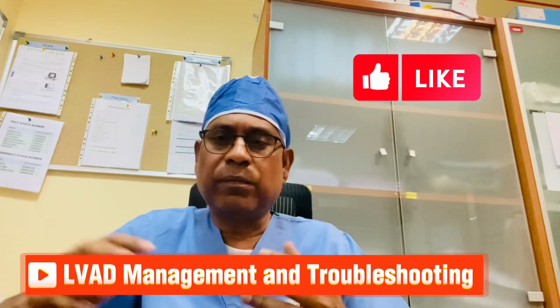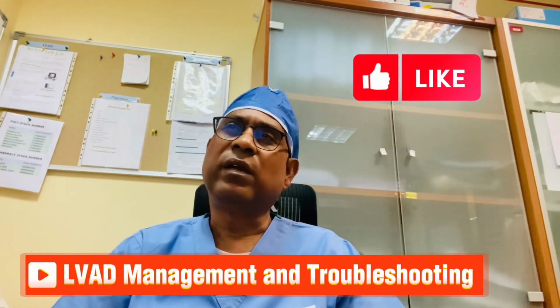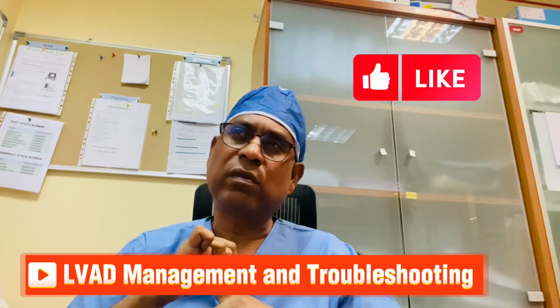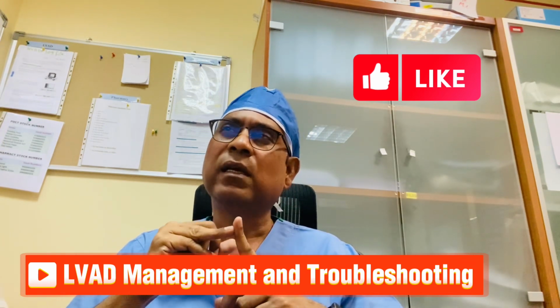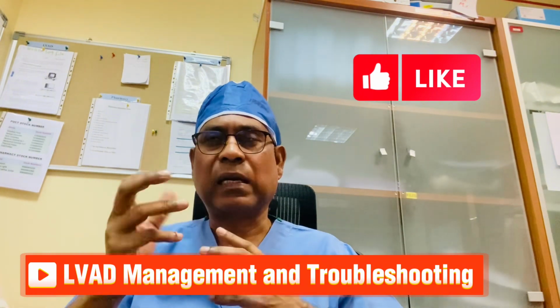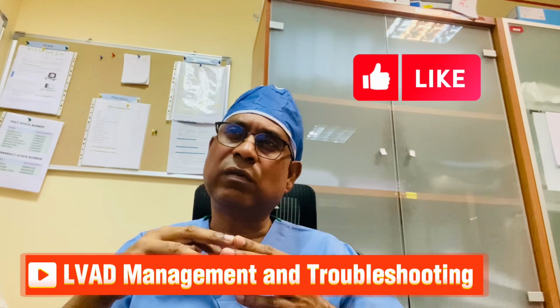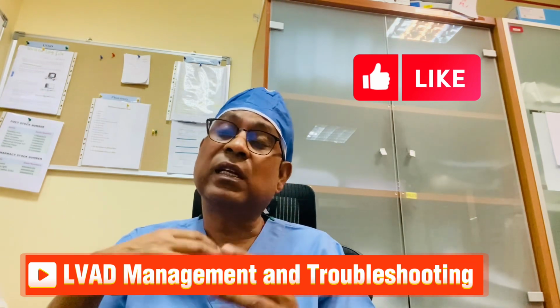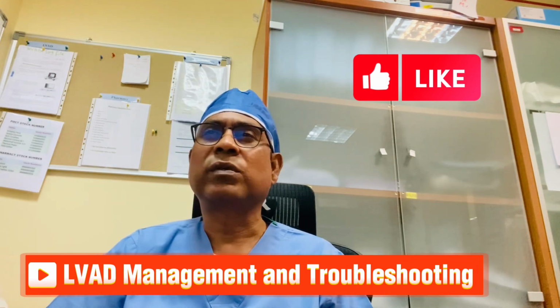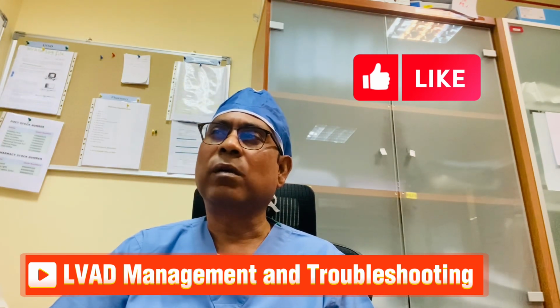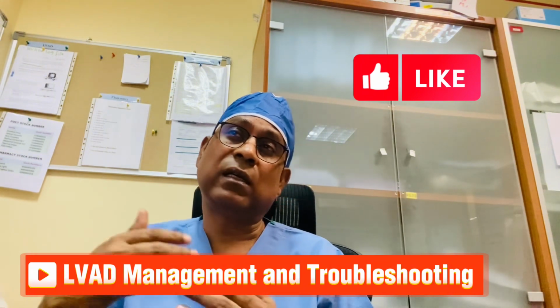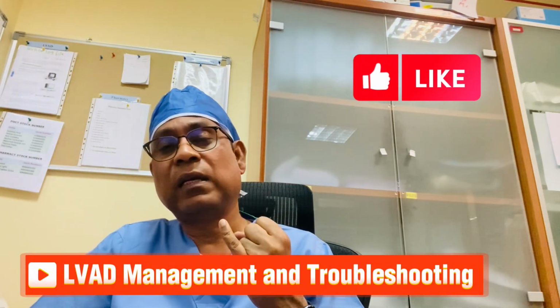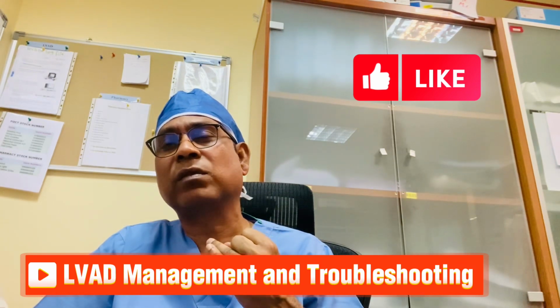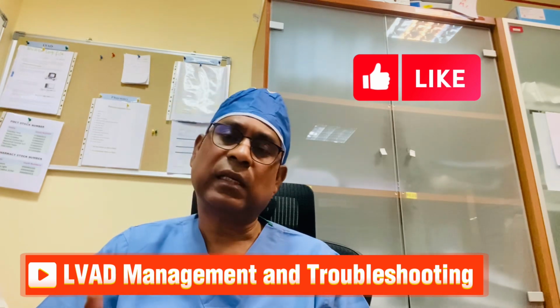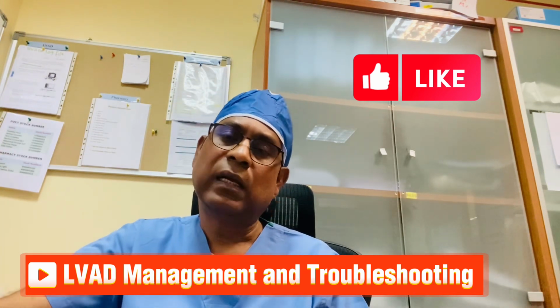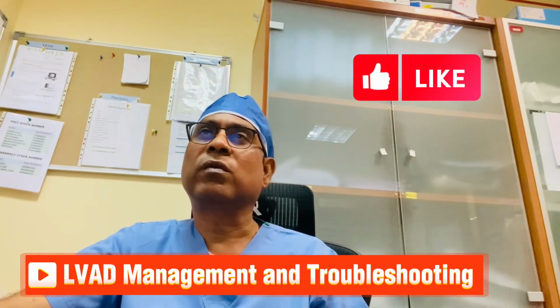When the patient is going home, the LVAD patient will receive one system controller and two sets of batteries, a primary operating set and a backup battery as backup support. The power base unit and control monitor are required at the initial implantation and subsequently when encountered to review the settings and alarms, but are not required components to be handed over to the patient at discharge. Normally we give one extra pocket controller and two extra batteries to the patient, and even the battery charger. So the patient has the battery chargers, two backup batteries and power, and one pocket controller.